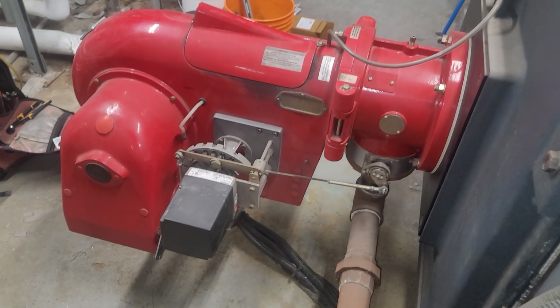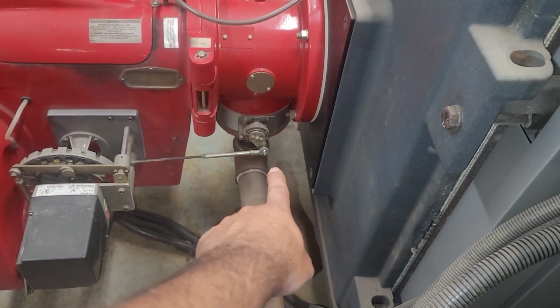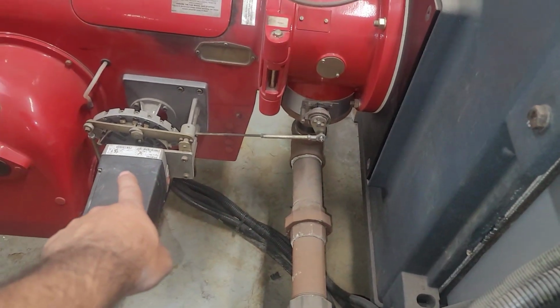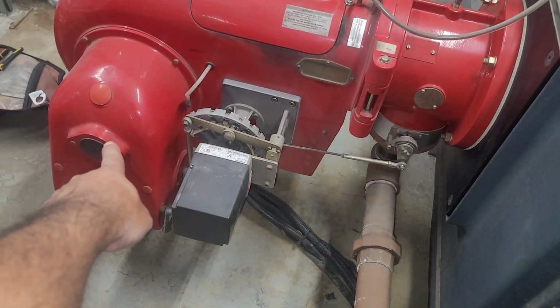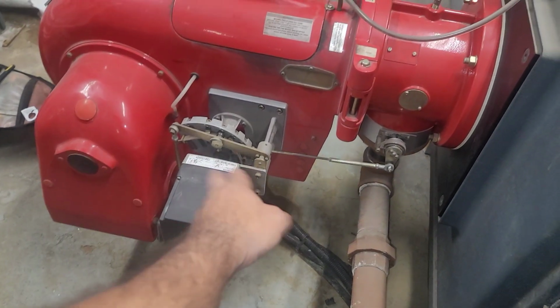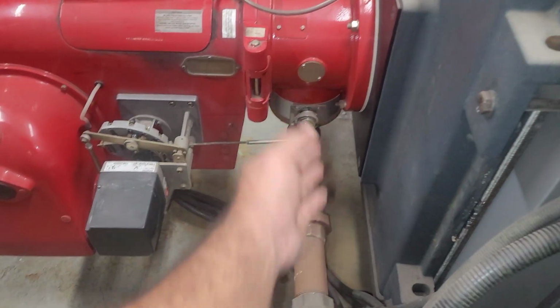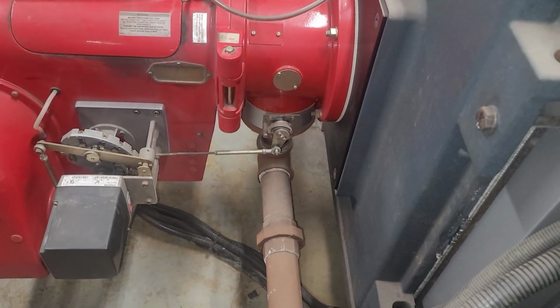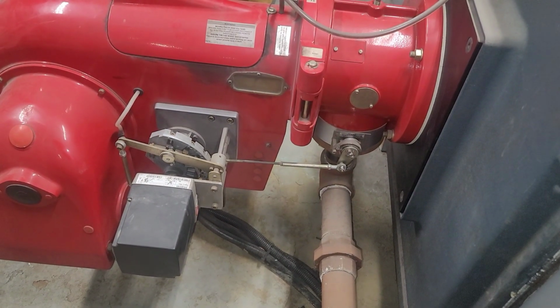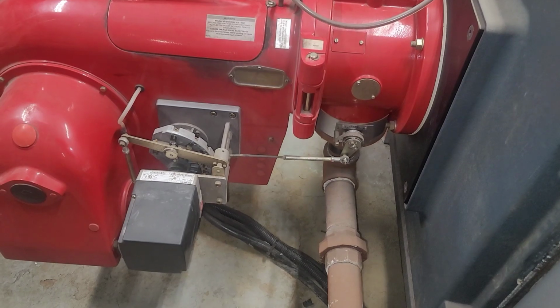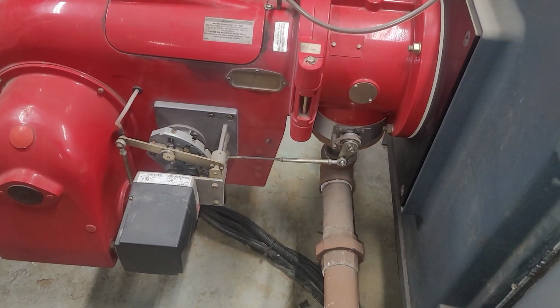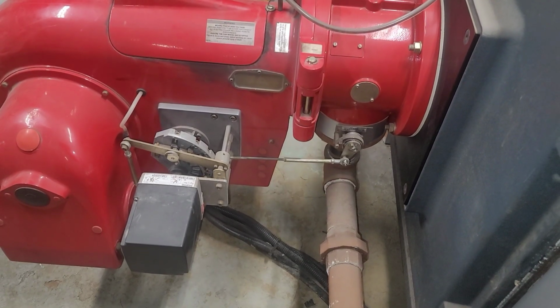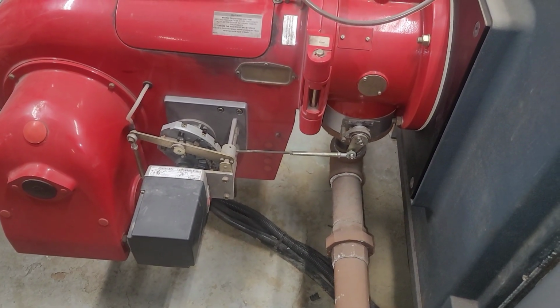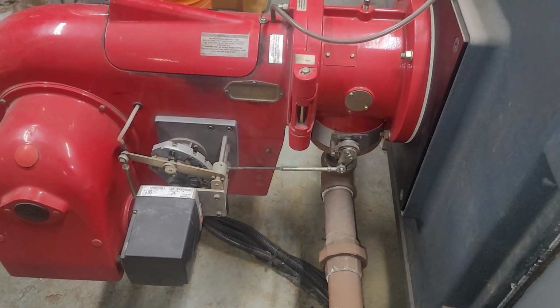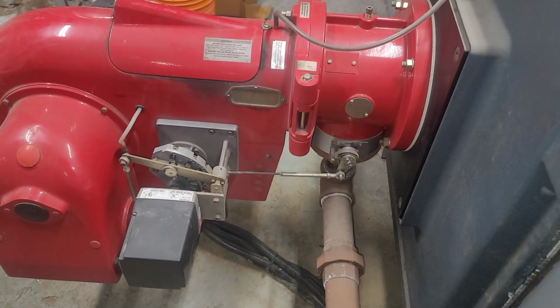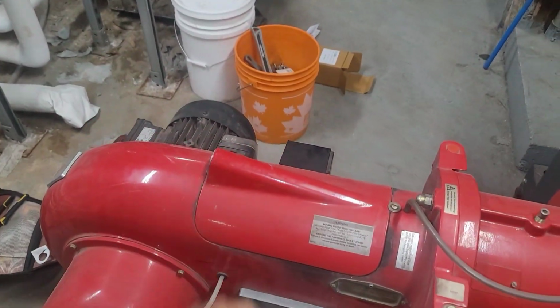Okay, so our blower motor started, and this is the opening and closing of gas fuel, and this opening is also connected to the air. So this linkage ensures the proper air and fuel ratio going into the burner. Right now it's doing its pre-purge, and once the pre-purge is done, then it will go for ignition trial. It's very loud. That's a 3-phase high voltage motor.